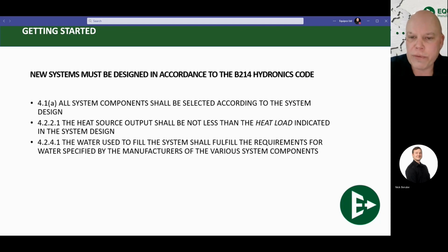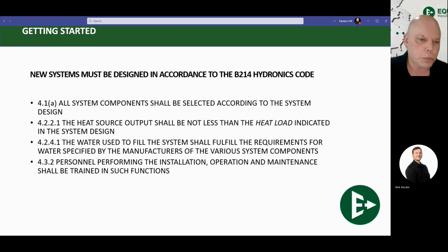4241, the water used to fill the system shall fulfill the requirements for the water specified by the manufacturer. If you were to read the installation manual for the boiler that you are currently selling, doesn't matter who, doesn't matter what, all of these folks are going to list in their manual what they need for water quality. They will list the pH of the water between 7 and 9 or something like that, or 6 and 9, whatever it's going to be. Everybody's a little bit different. The total dissolved solids, how many parts per million of particulate they will allow in the water. Your maximum glycol percentage that's allowed in the water. All these things have to be done correctly by the manufacturer's installation instructions, required by code.